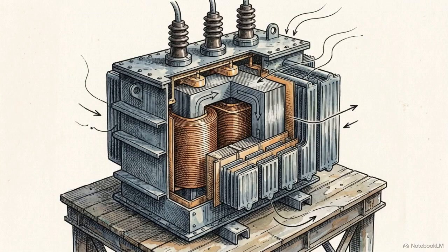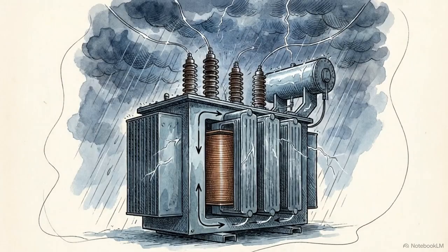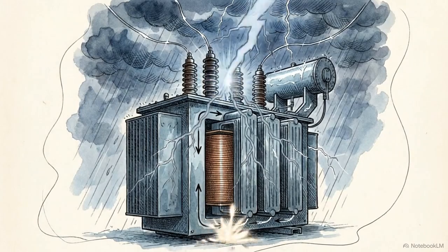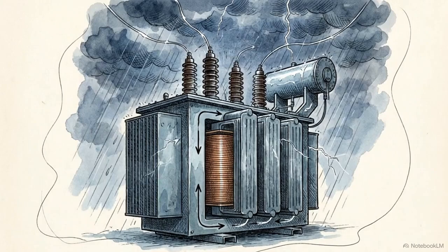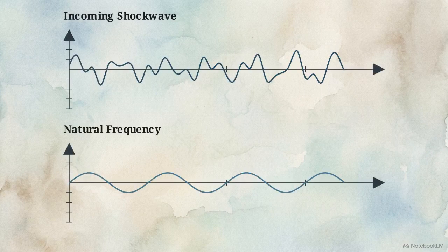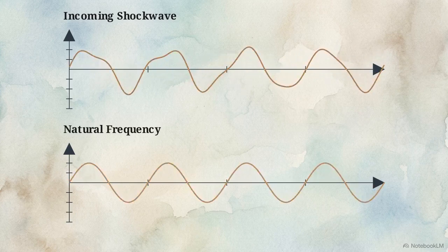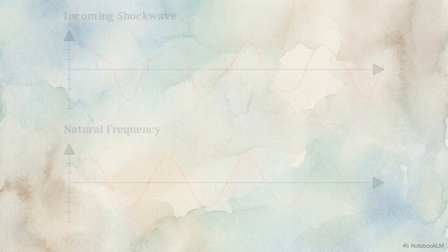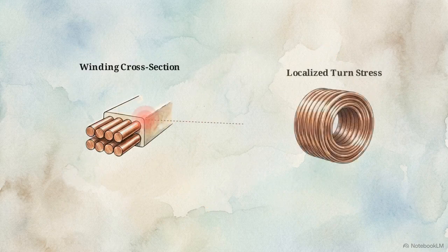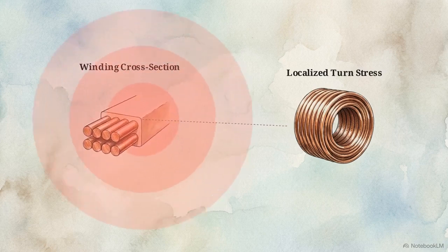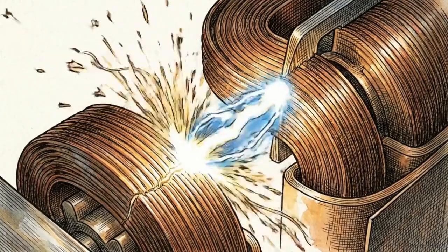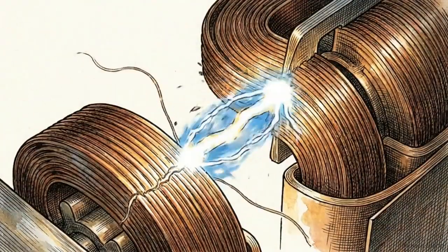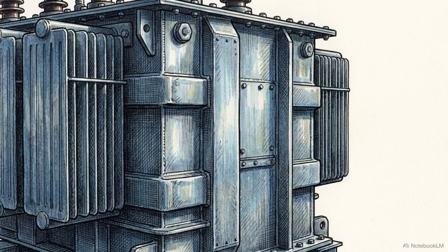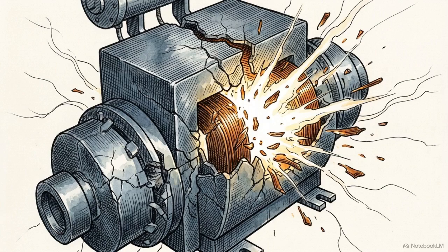network. Those high-frequency shockwaves travel along the cable until they slam into the wind farm's step-up transformer. Normally, a transformer is guarded against outside threats. Standard external insulation easily repels traditional dangers, like a lightning strike on an overhead line. This visualization shows the mechanism of destruction: internal resonance. The incoming switching shockwave overlaps exactly with the natural vibrating frequency of the transformer's copper windings. Because these frequencies sync up, voltage amplifies locally, multiplying its power far beyond what internal materials can handle. The trapped voltage builds until it violently flashes over, arcing directly between the winding discs and bypassing all the standard insulation. The high-frequency transient doesn't break the door down from the outside. It acts like a targeted acoustic weapon, shattering the transformer from the inside out.